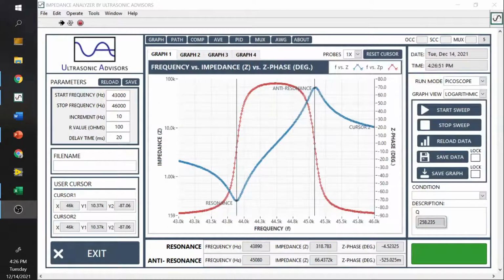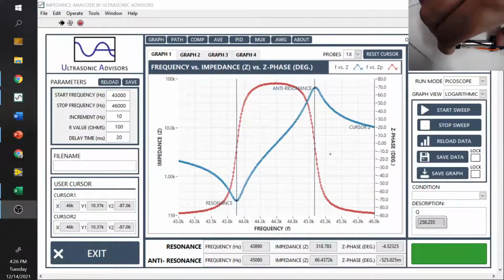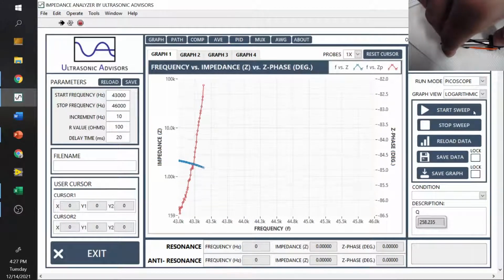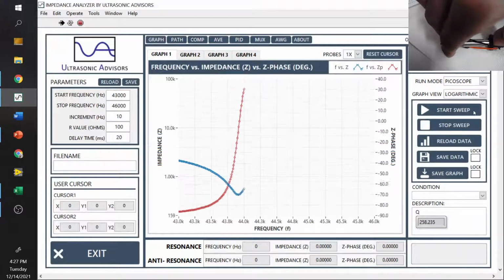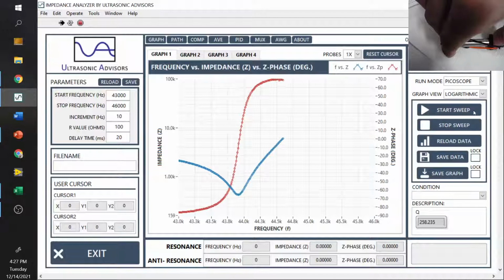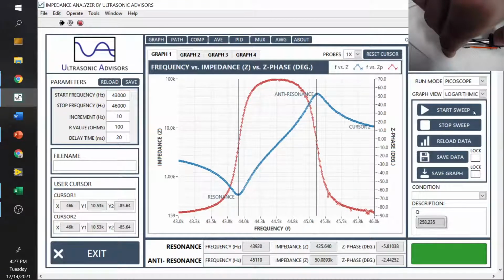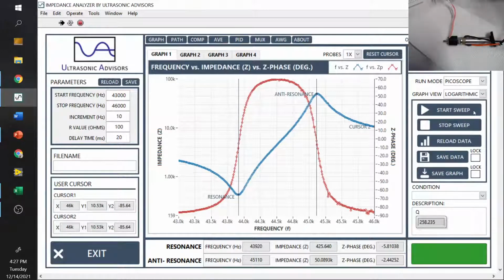You only live once, so let's make this happen. I'm going to hold it like that, and let me just reduce that size so you know what I'm doing. I'm holding it there just like it would be held inside of the holder. So let it do its thing. The black plastic part on the front is pushing back against the O-ring, which is pushing back against the base of the horn of the transducer, and then the back is supported by a pad and a plastic piece. All right, so let's now push that button.